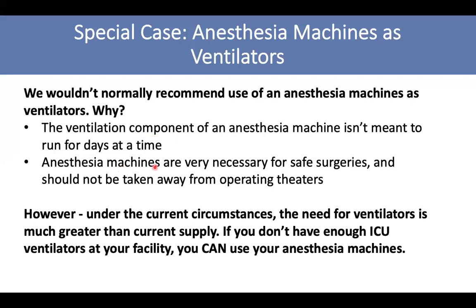Anesthesia machines are very necessary for safe surgeries and should not be taken away from the operating theaters. However, under the current circumstances, the need for ventilators is much greater than current supply. So if you don't have enough ICU ventilators at your facility, you can use your anesthesia machines.